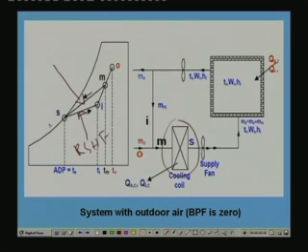Process MS. This depends upon the ratio of sensible and latent heat loads at the coil. So, you can define what is known as the coil sensible heat factor, CSHF, as the sensible heat load on the coil divided by the total heat load on the coil.